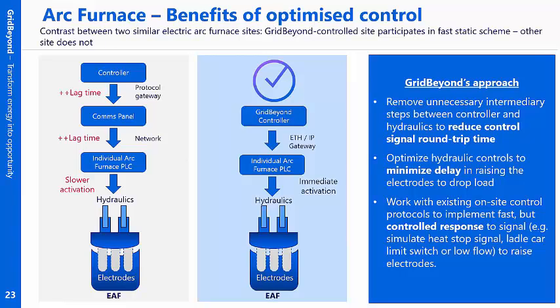Another option would be a critical alarm, such as lost cooling water. By us sending an input into your arc furnace PLC, and the third-party control taking that input and triggering a heat stop signal or a lost cooling water signal, this all stops the arc furnace within 1 second.